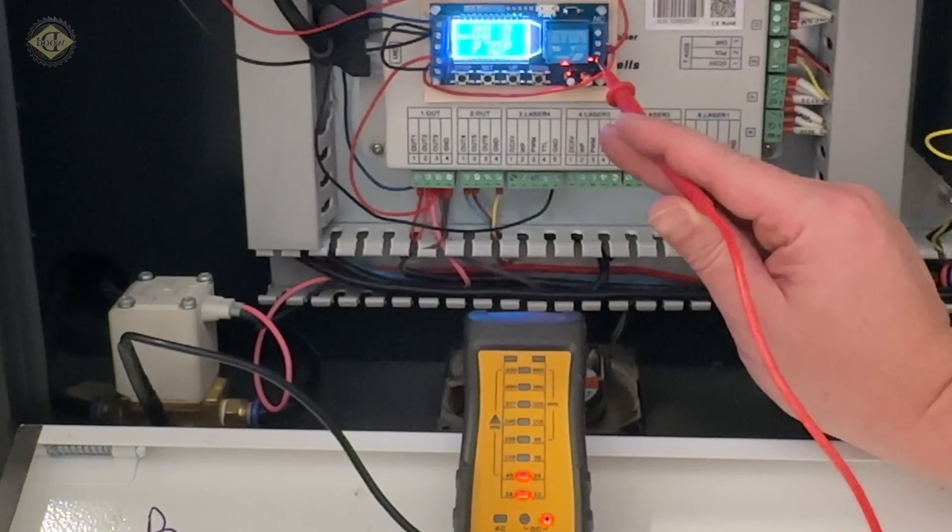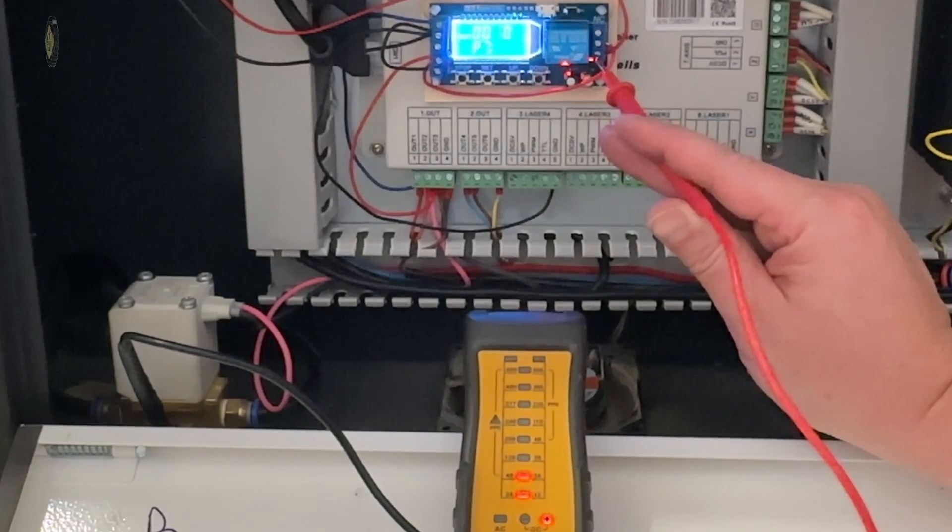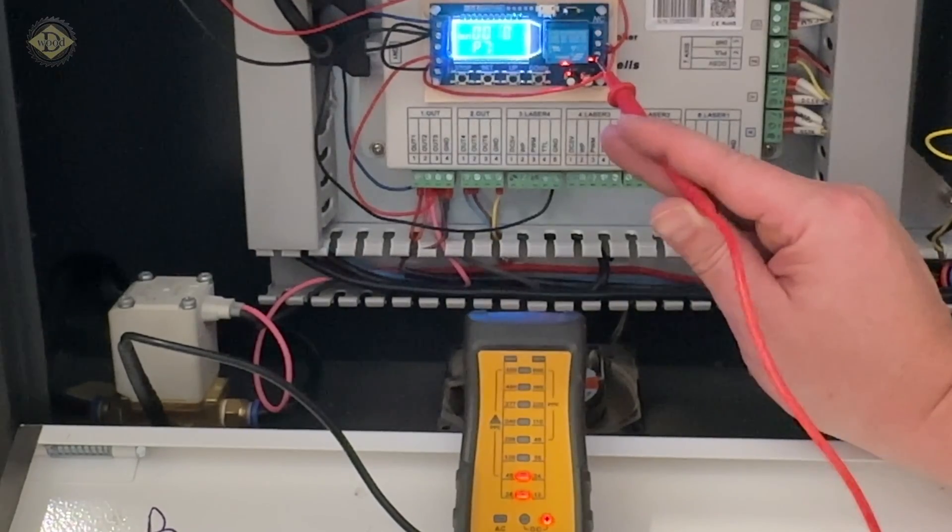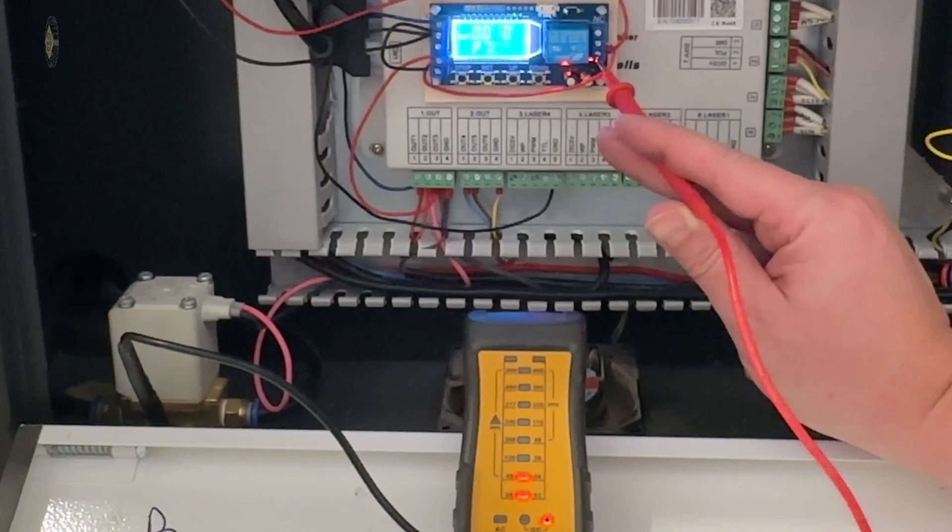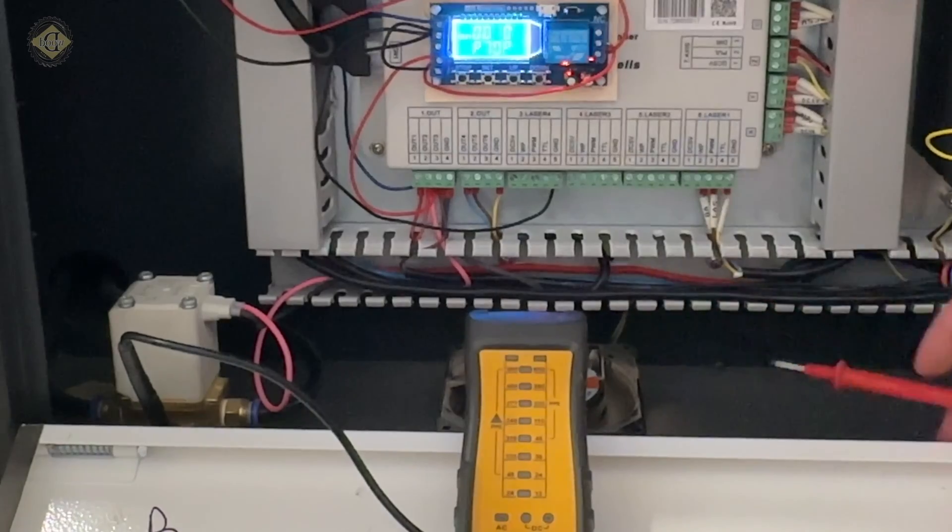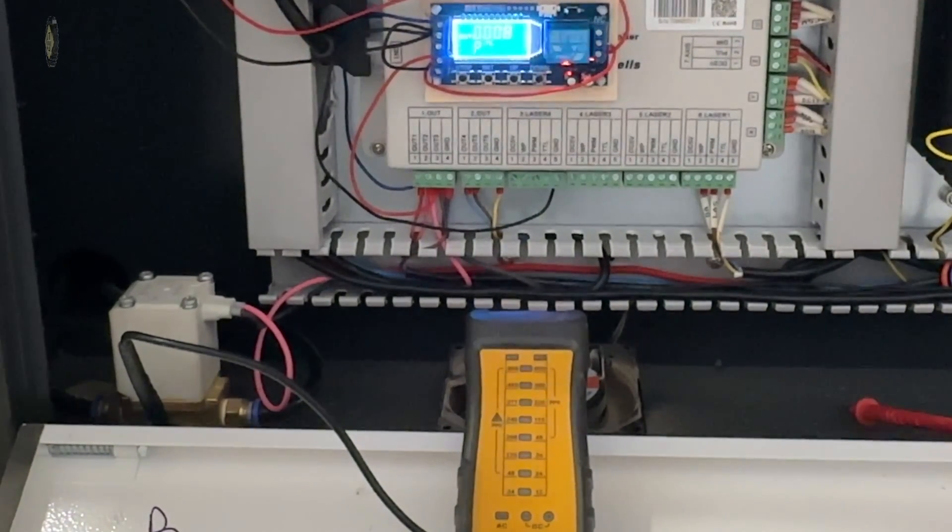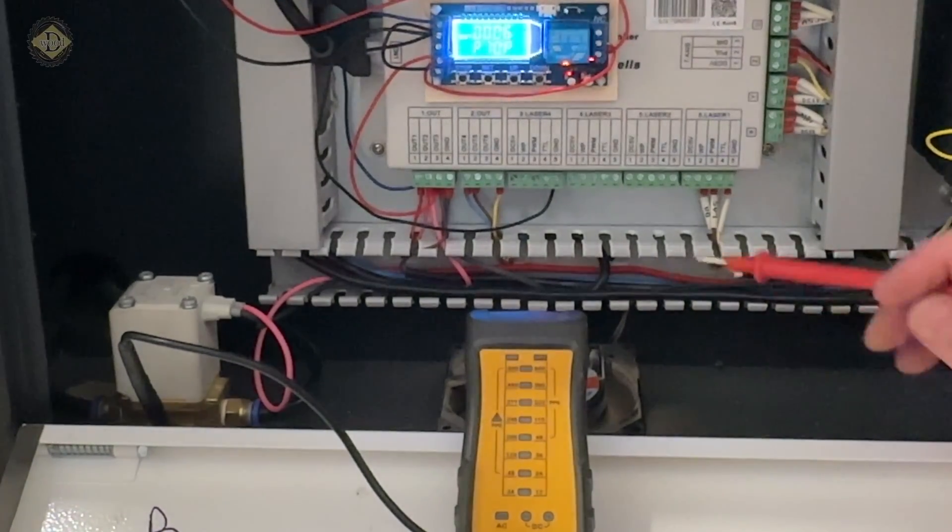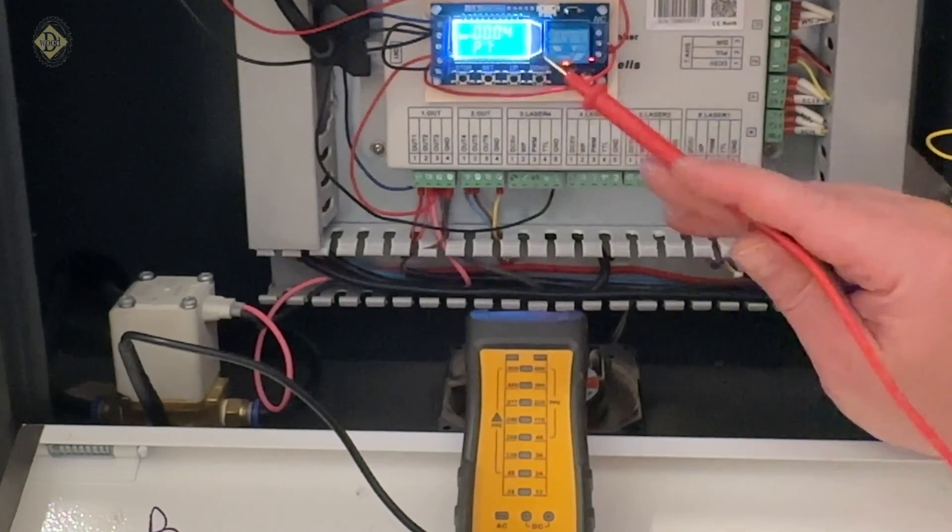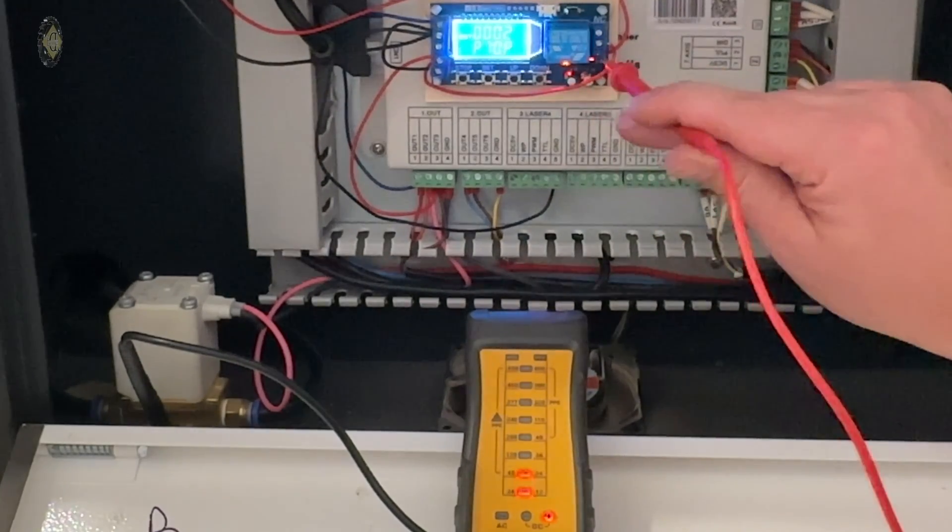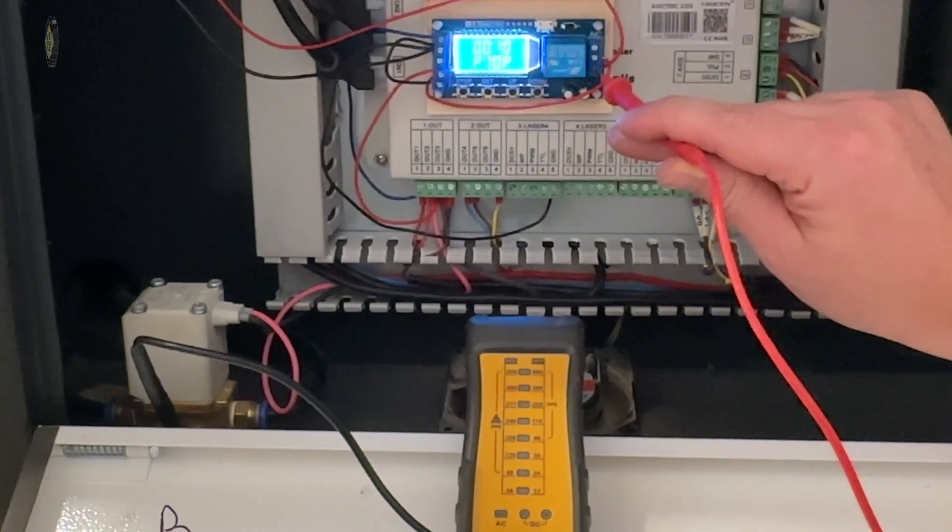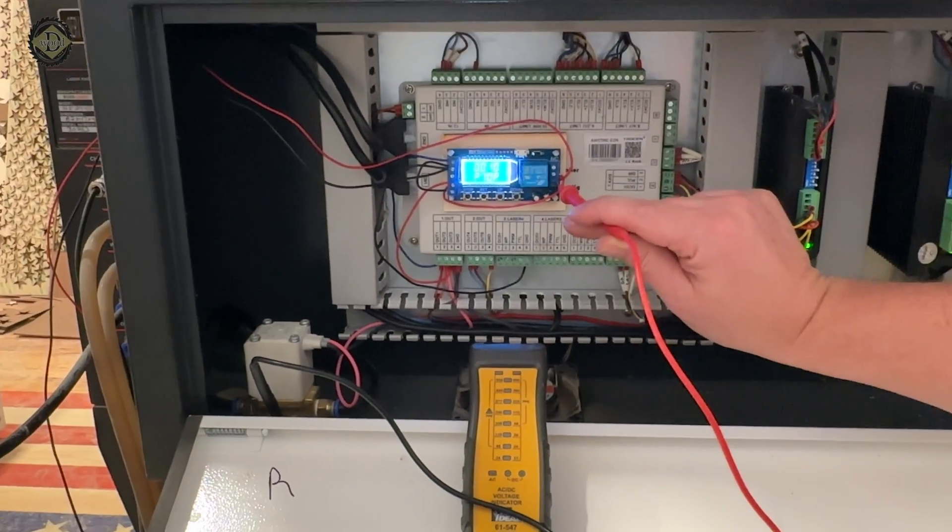Now, let's see if I can get back here fast enough after shutting the job off, hitting stop, and show you that it delays for 10 seconds. As you can see, it's counting down, we have power, and the relay shuts off, and we no longer have power, which will shut the fan off.